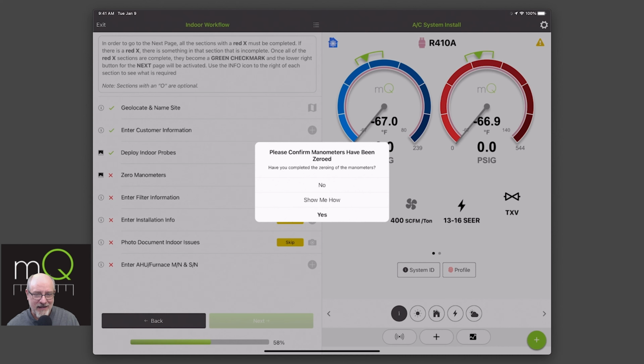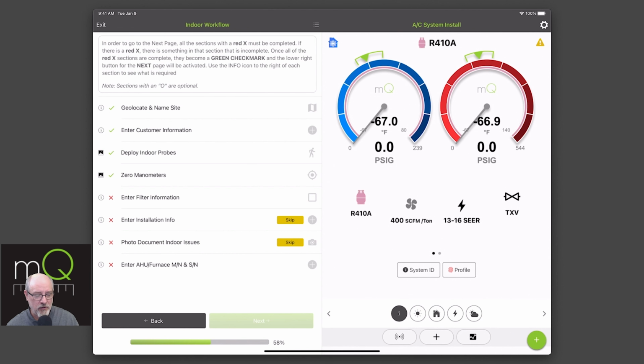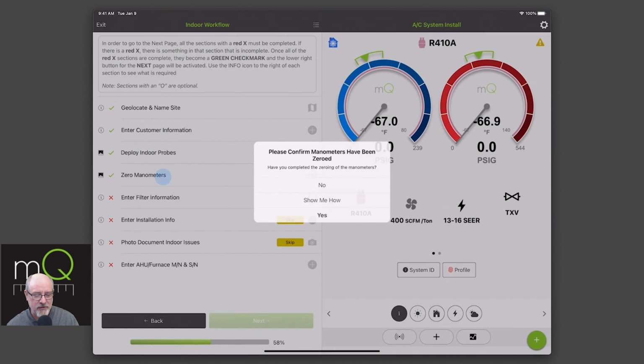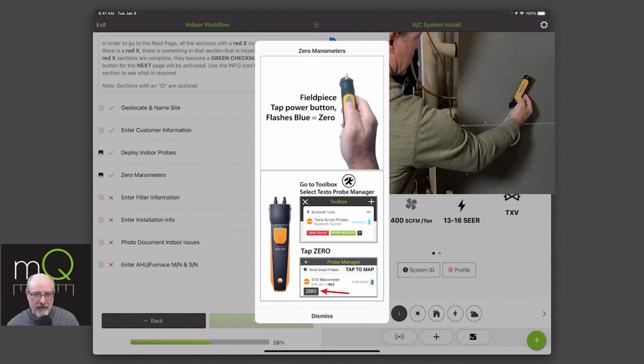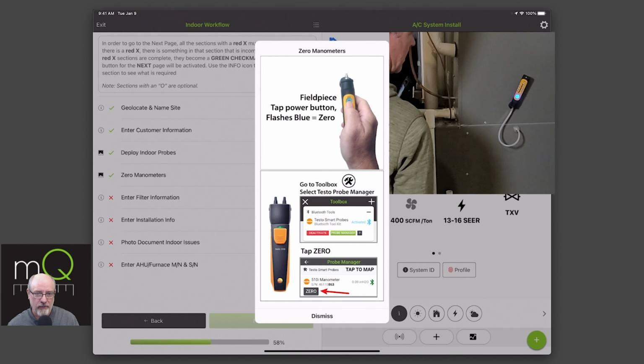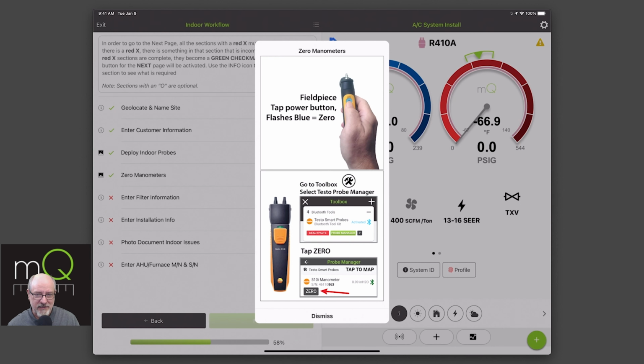This does not zero your probes. Just to clarify, the probes are actually zeroed for a Fieldpiece on the device, and for a testo they're zeroed in the app in your toolbox. So if I did zero them, I hit yes. If you're not sure or want to see what to do, you can click on the picture over here, or in the zero manometers it says 'show me how', and there's a quick picture of how to zero the Fieldpiece and the testo in the probe manager, the toolbox.